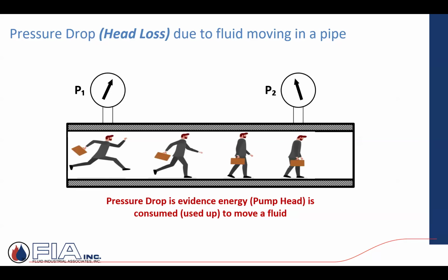Kind of an interesting slide. Some people can appreciate what they're trying to show here, but they're saying as water's moving through that closed loop system and it has this energy that's been added to the water as it passed through the pump, if you have gauges throughout the system, those gauges are going to reflect a drop in pressure. That drop in pressure is just evidence that there's been work done. There's been energy consumed to move the water through, in this case, the piping system, this frictional resistance. How much? Well, we calculate that. We figure it out. And then we pick a pump that can move the flow rate based on the BTUs and overcome the frictional resistance of that closed loop system.